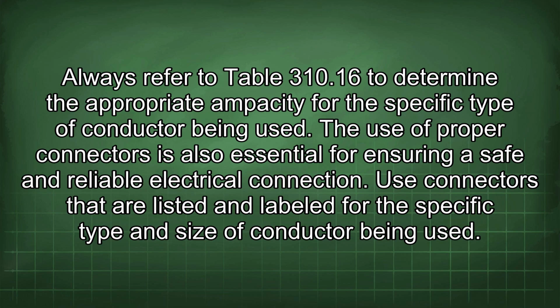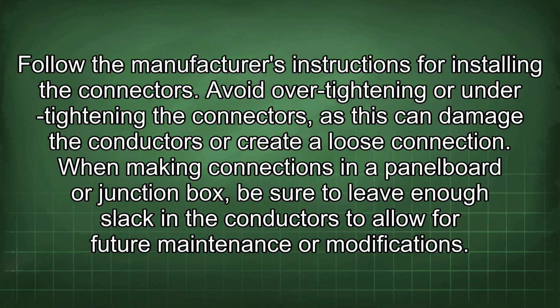The use of proper connectors is also essential for ensuring a safe and reliable electrical connection. Use connectors that are listed and labeled for the specific type and size of conductor being used. Follow the manufacturer's instructions for installing the connectors. Avoid over-tightening or under-tightening the connectors, as this can damage the conductors or create a loose connection.